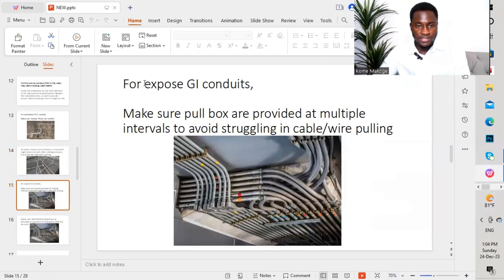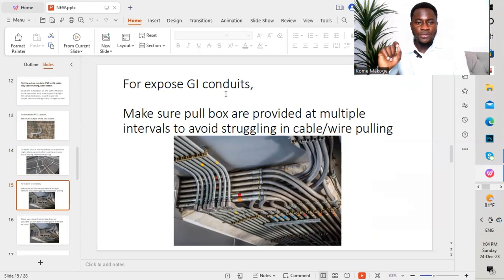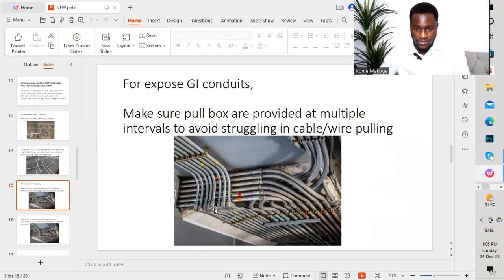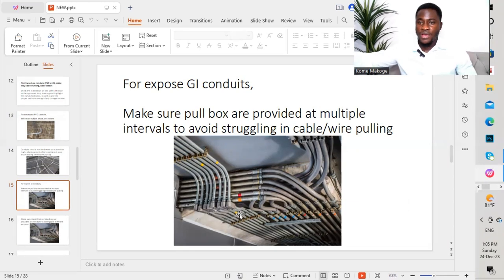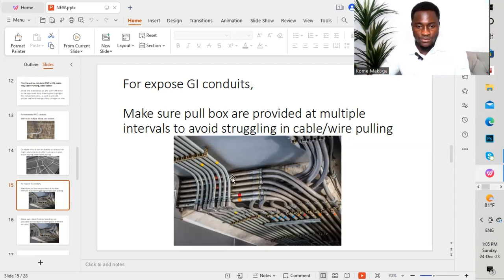Moving to the third point: for exposed GI conduits — where we have galvanized iron conduits — you make sure pull boxes are provided at multiple intervals to avoid struggling during cable or wire pulling. As shown in the graphic, we have pull boxes on this EMT conduit installation. We provide pull boxes or pull areas so that when we are pulling cables, we can stand from one point and pull to the other side. For example, if we have a length of 10 meters with a straight conduit but with bends in certain areas, we need to provide pull boxes to avoid issues while pulling cables or wires.